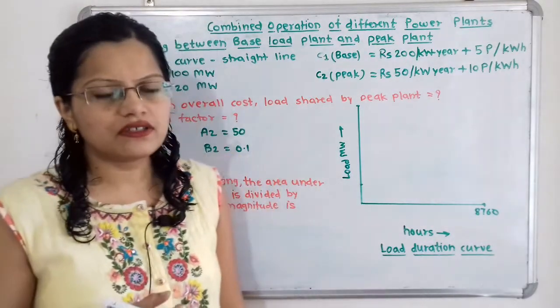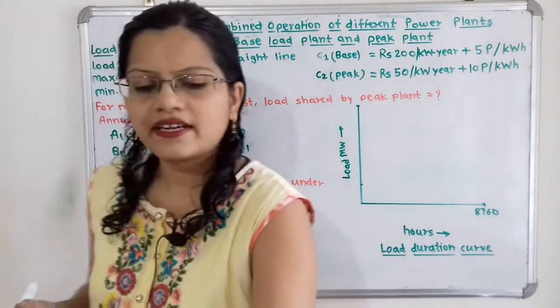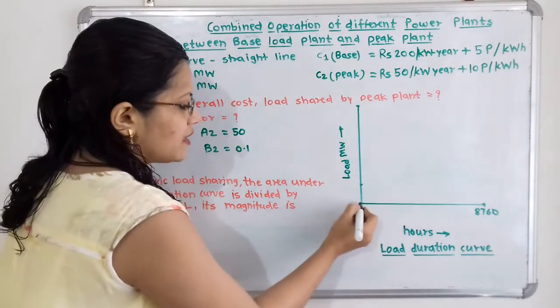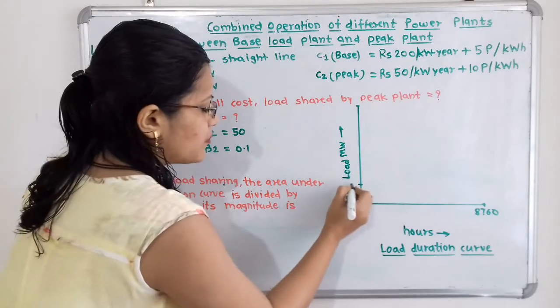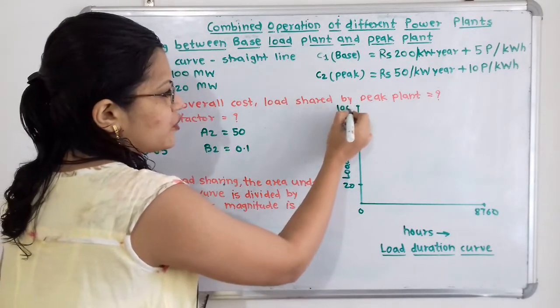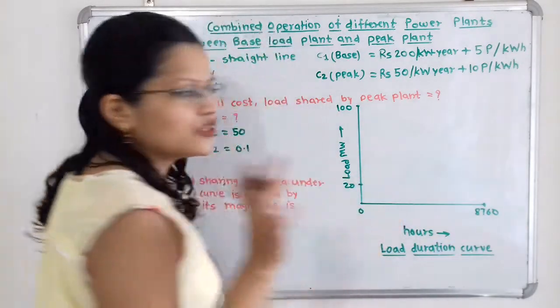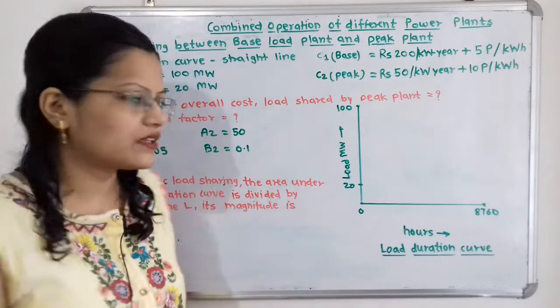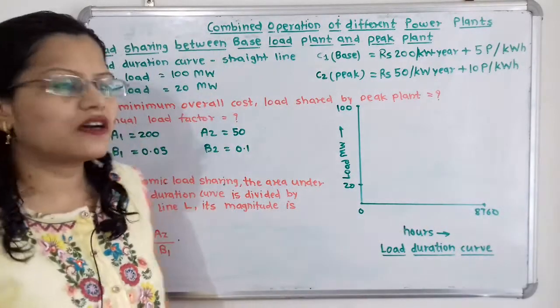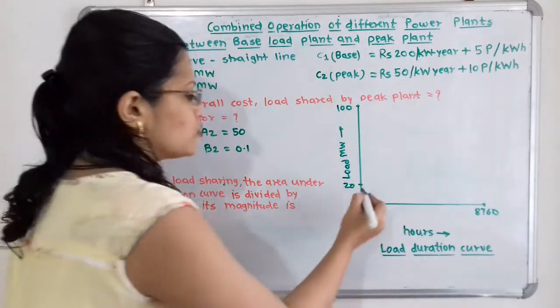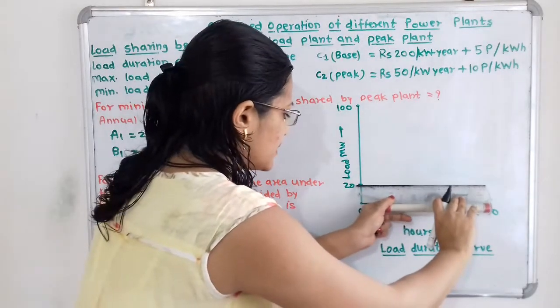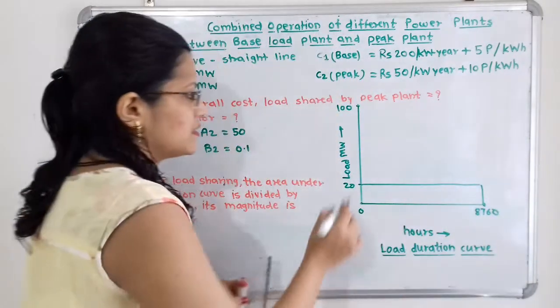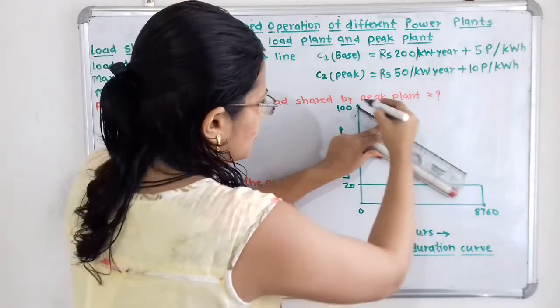Now we will draw the load duration curve. As per the given data it is in the form of a straight line and varies from 100 MW to 20 MW. We will draw a vertical axis starting from 0, with 20 MW and 100 MW marked. On the horizontal axis we take the duration in number of hours. Since installed capacity is for one year, the number of hours in one year is 8760. The load duration curve varies between 100 MW and 20 MW, so we draw a horizontal line passing through 20 MW at a magnitude equal to 8760 hours, and complete the straight-line load duration curve.